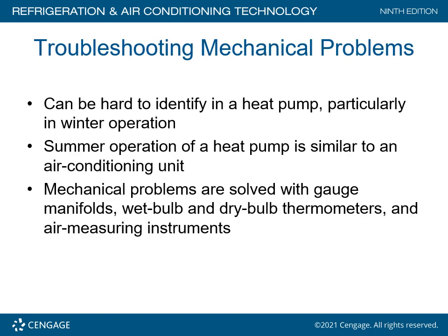Troubleshooting mechanical problems can be hard to identify in a heat pump, particularly in winter operation. The hardest thing you're going to find is how to charge a heat pump unit in the winter, when the refrigerant charge is typically going to be about 60 to 70% versus the full 100% that the unit was rated for in the summertime. Summer operation of a heat pump is similar to an air conditioning unit, so that's pretty much a no-brainer. Mechanical problems are solved with gauge manifolds, and I might add electronic gauge manifolds, wet bulb and dry bulb thermometers, and air measuring instruments.